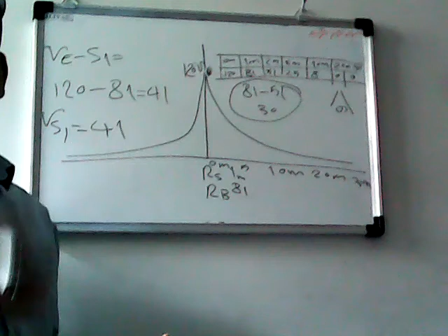The more you move away from your earth electrode, the more your step voltage will be less. Until that place, you should do the measurement. Until that place, 20 meter over here, 30 meter, will be zero. After you find the zero step voltage, you surround it with fans and something like warning alarm lights to pay attention. The other person here may be in danger. In that time, our protective equipment didn't act.